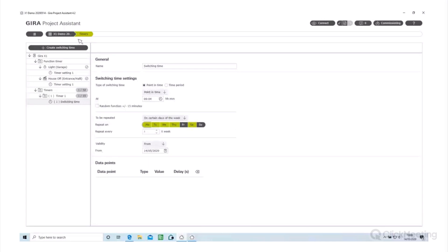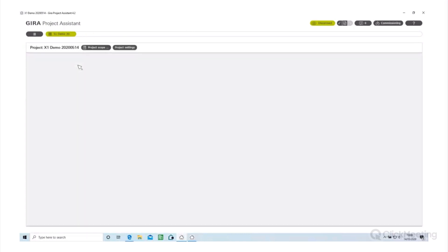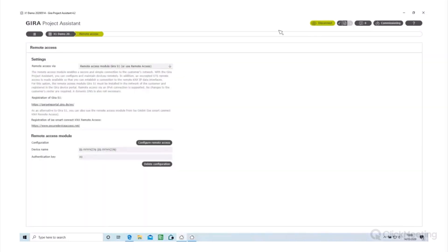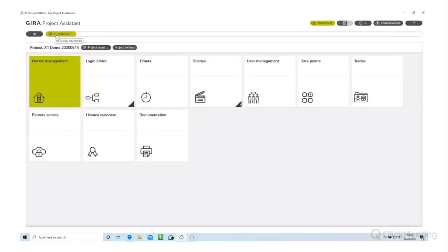Another update is the Connect button, which activates remote access. If you're using the Gira S1 for remote access to your installation, you make the settings in the Remote Access tab from the main tile. Once you've made the connection in ETS, it will automatically see the connections - you don't need to install the standalone Gira program. Simply open GPA, enable remote access with the Connect button, and ETS will see the remote IP connection straight away - no messing around with VPNs.